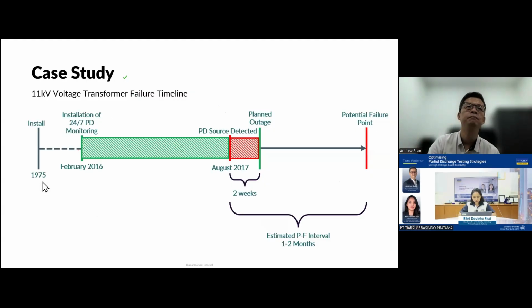If you look at the case study, the switchgear was installed in 1975. In 2016, when we started talking to them, they realized that since they cannot change the switchgear, they had better do something to monitor it and tell them if it has a problem, because it is already so old. By 2015 it was already a 40-year-old switchgear. So in February 2016 we installed, and we moved on. 1.5 years later, we detected PD.